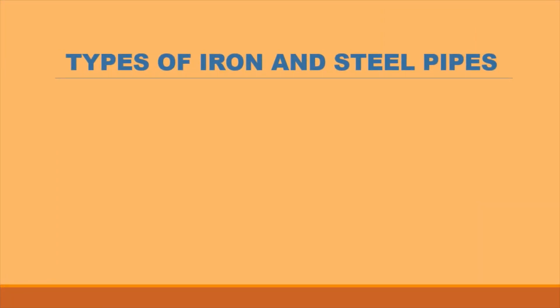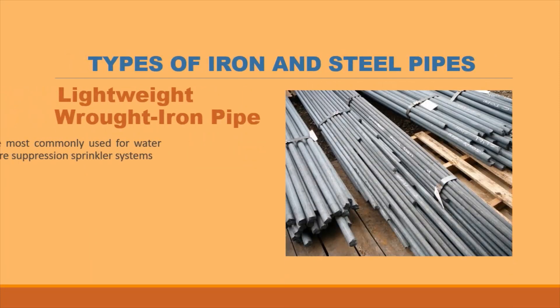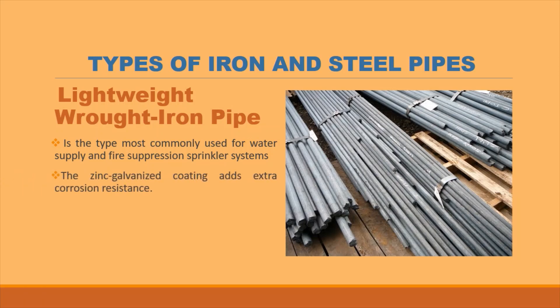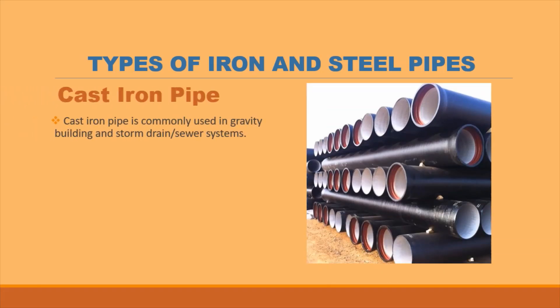There are three types of iron and steel pipe. Galvanized steel pipe is covered with a protective coating of zinc that greatly reduces its tendency to corrode, extending its life expectancy. It is moderately corrosion-resistant and suitable for mildly acid water. Lightweight wrought iron pipe is most commonly used for water supply and fire suppression sprinkler systems; the zinc galvanized coating adds extra corrosion resistance. Cast iron pipe is commonly used in gravity building and storm drain sewer systems, and is limited to gravity pressure systems.